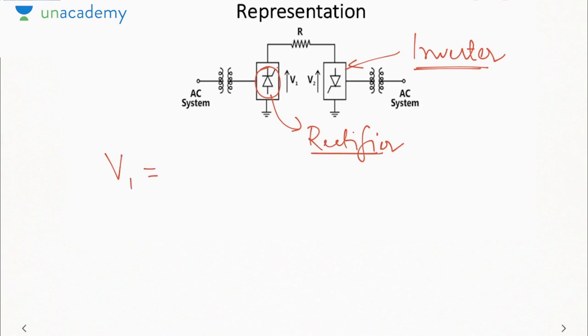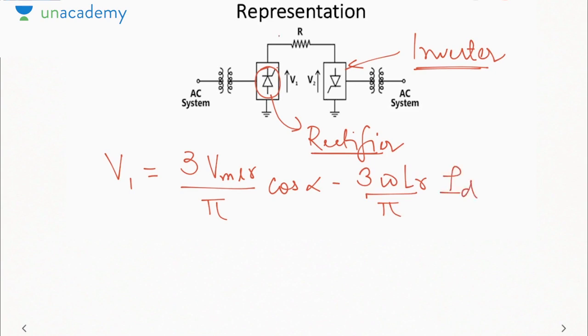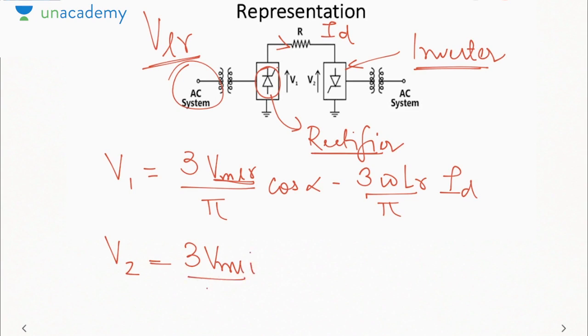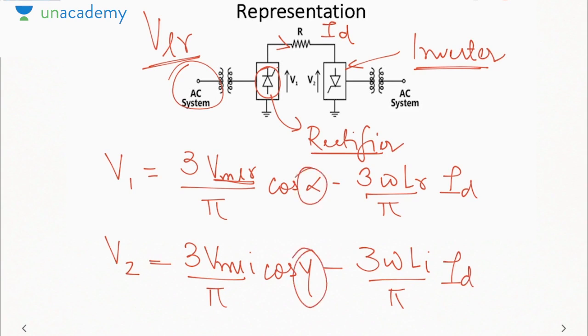Now the DC output voltage of a rectifier, V1, is always 3 VMLR by pi cos alpha minus 3 omega LR by pi ID, where ID is the DC current flowing in the HVDC link. Here VMLR is nothing but the maximum line to line voltage on the rectifier side, that is here. So the maximum line to line voltage is VMLR, and V2 will be 3 VMLI by pi cos gamma minus 3 omega Li by pi ID. Gamma is the extinction angle of the inverter, alpha is the firing angle of the rectifier.